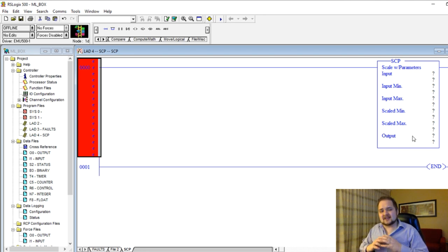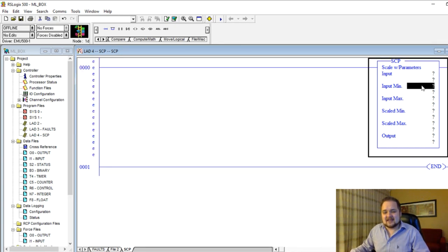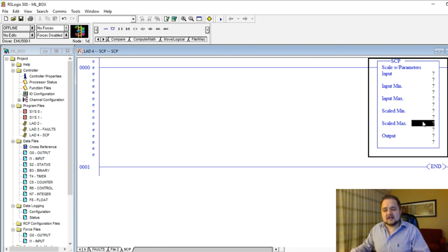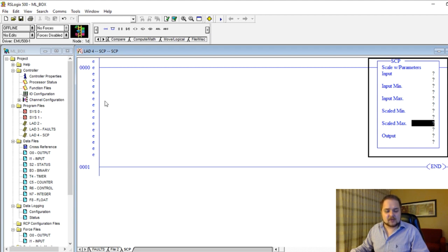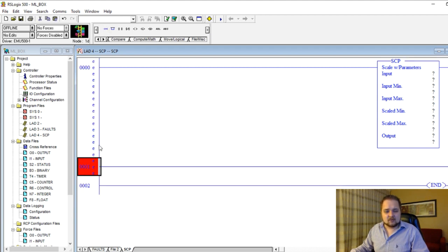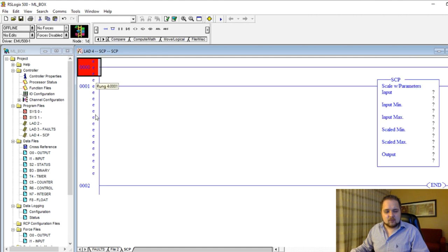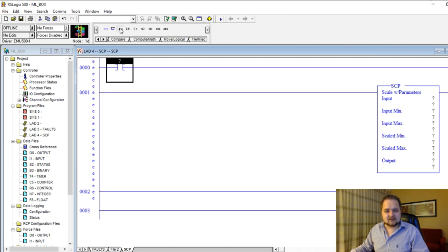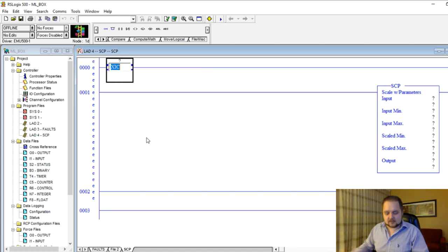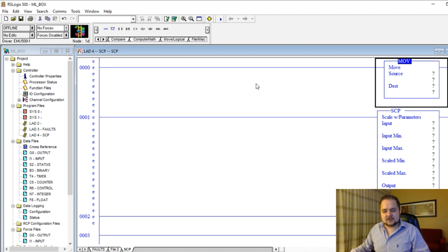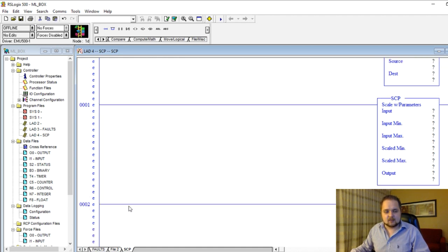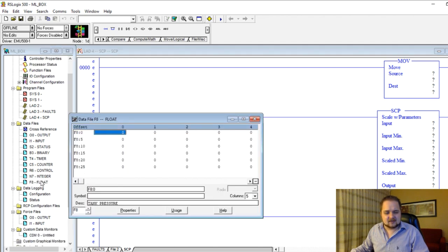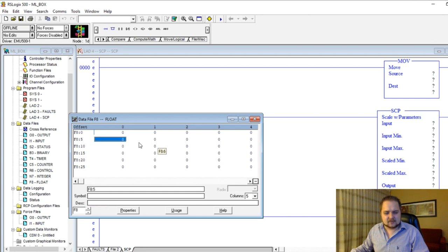So this is essentially a linear transformation which maps the input min to the scaled min and this input max to the scaled max, and everything else essentially gets approximated to that curve. So what I mean by that is we'll actually see this live in an example, but I do want to add two rungs here, one on top and one on the bottom so we can see that in action. So we're going to have a move instruction.